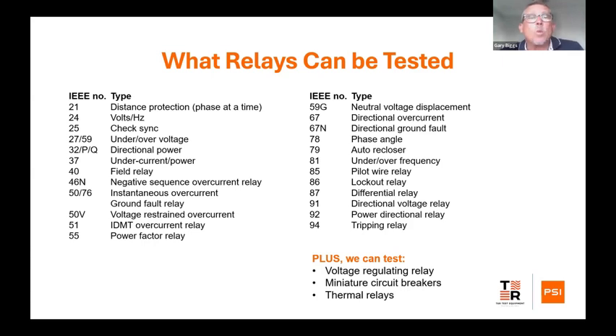So essentially, what relays can we test? What we do is, the numbers here, we've listed them as the IEEE numbers. Fortunately for us, the IEEE numbers and the ANSI numbers that you use out in Canada and the US match up. So when you're buying a relay test set, you can be confident that you've bought the right relay tester for the relays that you're testing, because there's nothing worse than buying a relay tester, going to do some testing, and then finding out that the relay tester you've just purchased doesn't test the relay that you want.